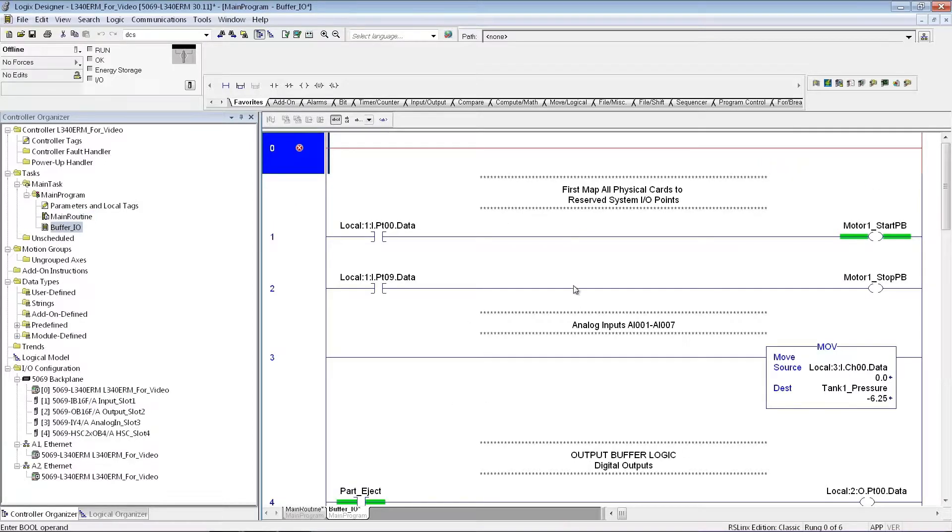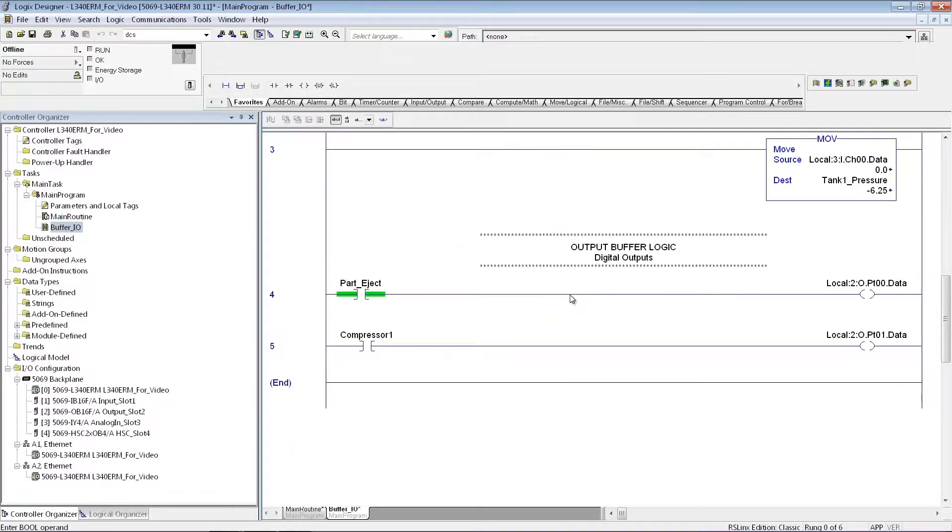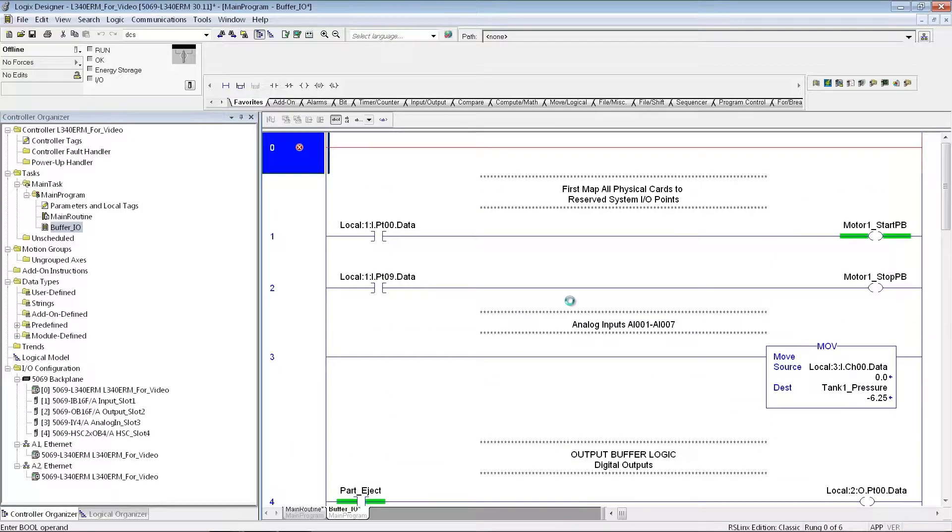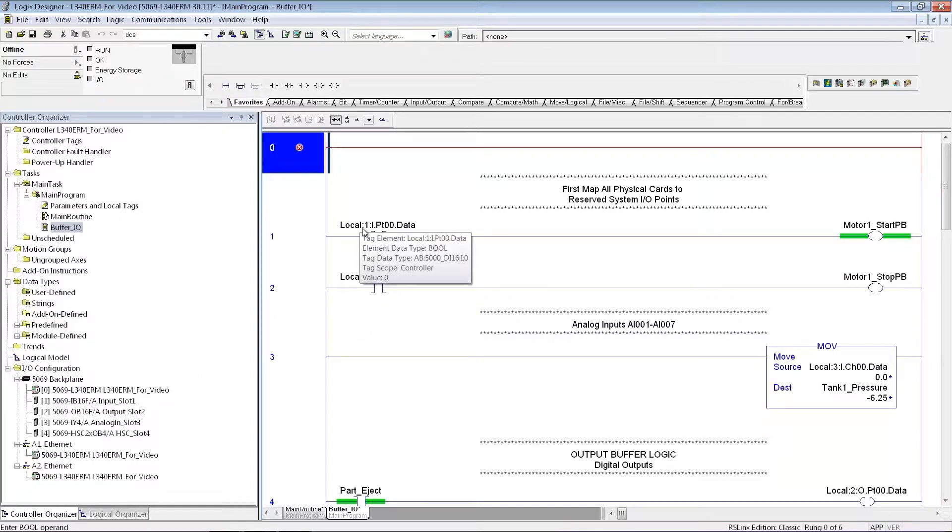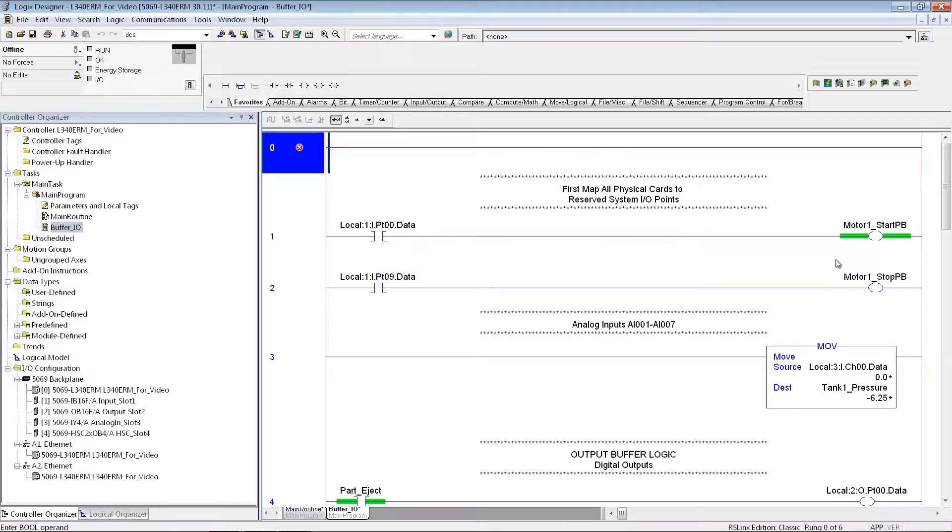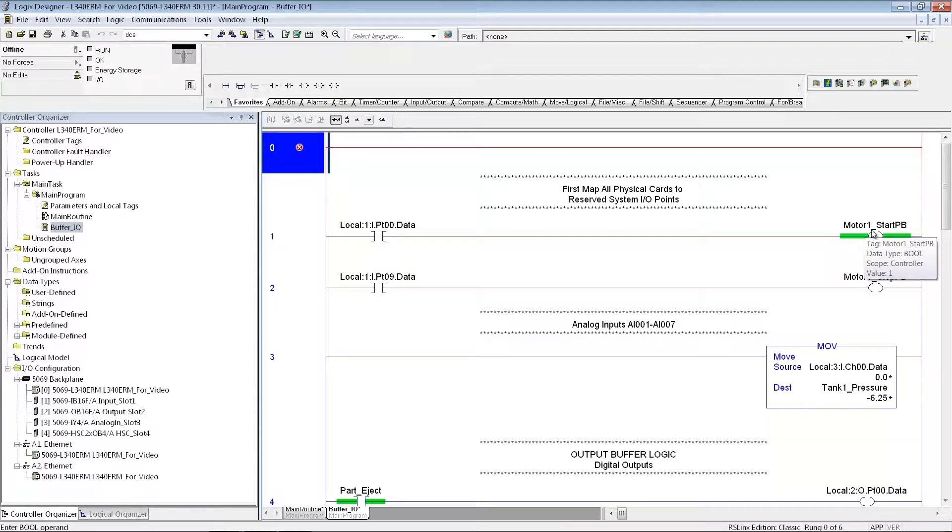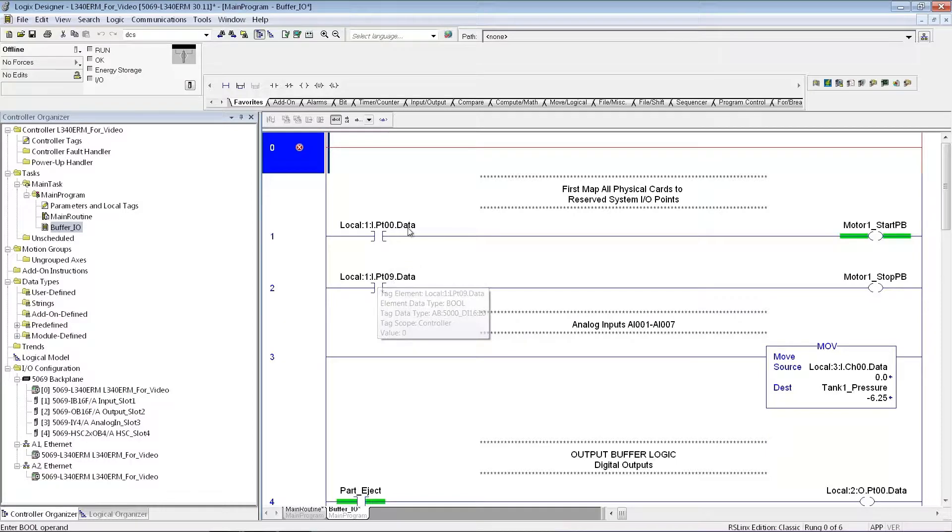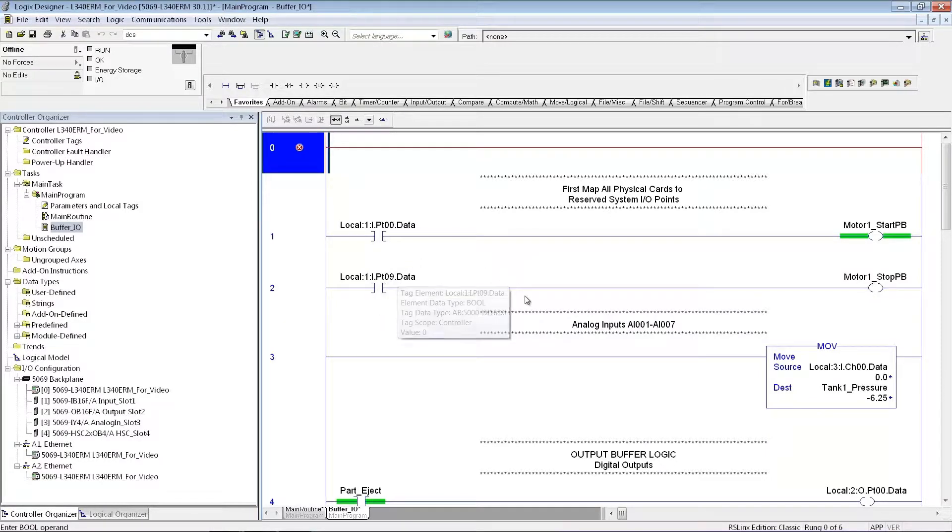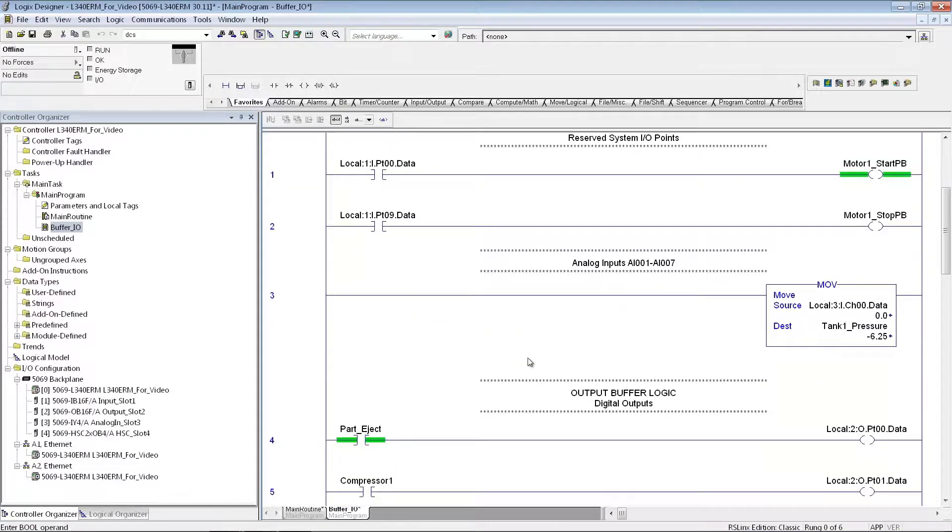I'll set up a Buffer.io subroutine, so that then I will just reference the tags that I create within the Buffer.io subroutine for the rest of my PLC programs. Buffer routine, I just put a few rungs just to show you how you would do that. Basically, what I'm doing is, this is an I.O. module that I'm getting from this slot right here, and I'm going to say, OK, whatever this is hooked up to, I'm going to give it a tag name. The tag name is going to be called Motor1_start pushbutton pb. I'm going to do that for all of the inputs in my program.